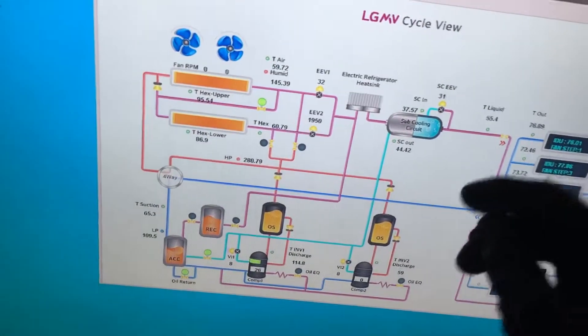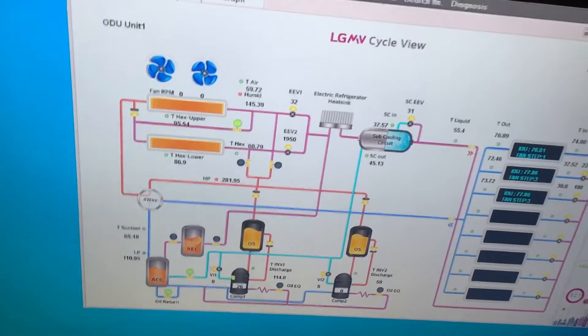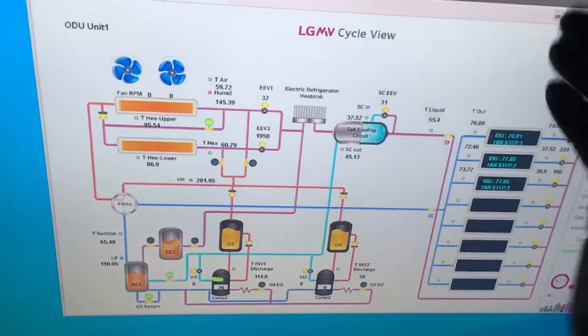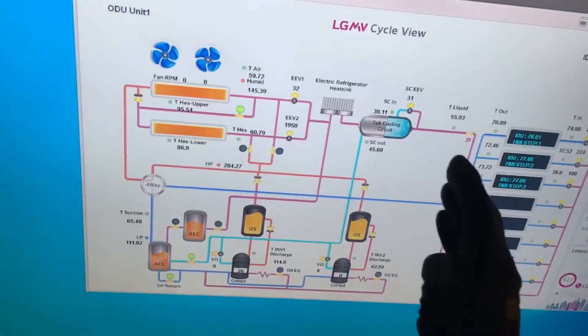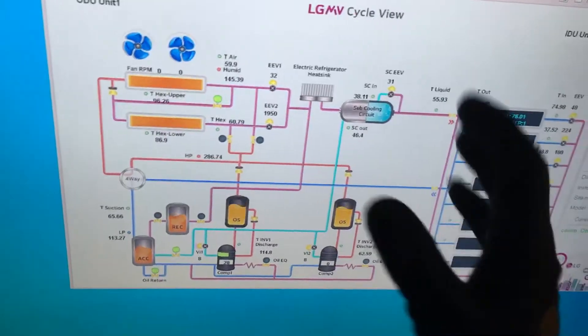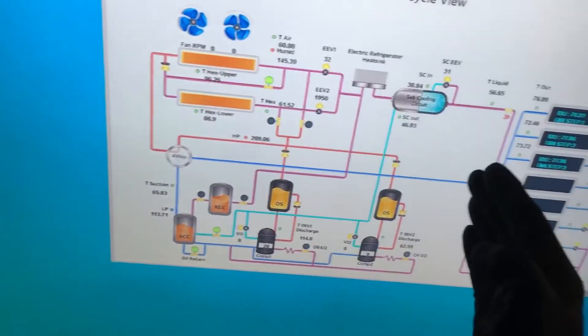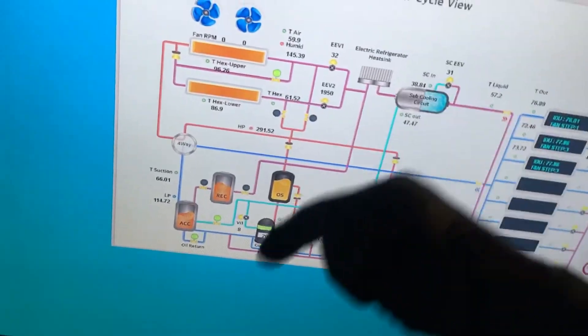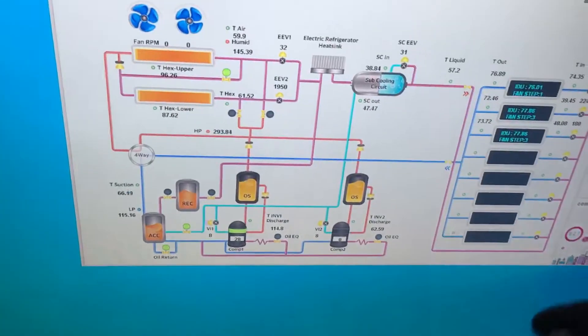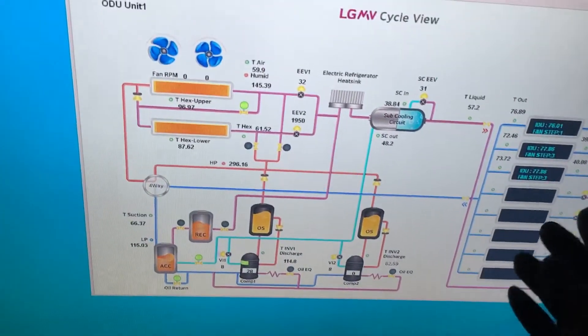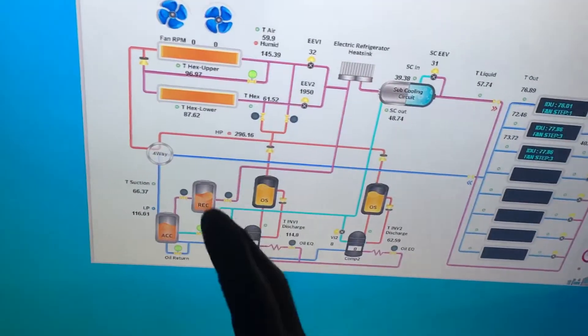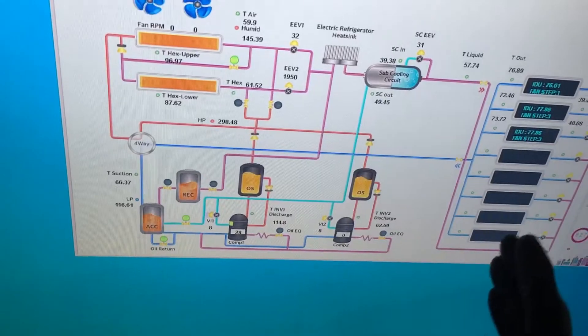Inverter driven motors, if you need say five tons of load all the time day and night, you do not get an inverter system and run it at full bore five tons. You become less efficient than if it was a regular system. You plan your system and spread out the load so you never run them all the time full bore, and that's what we're accomplishing here.